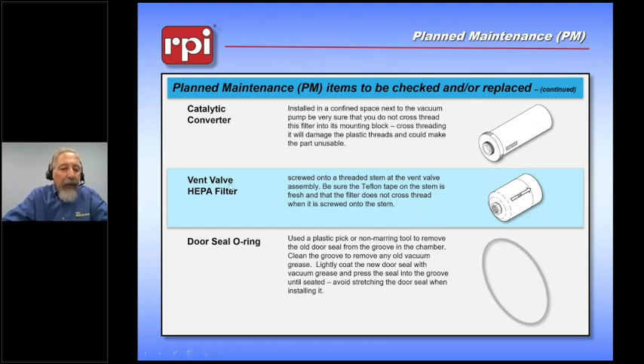Also included in the PM kit is a HEPA filter. This HEPA filter is what filters the main body of air that's allowed into the chamber when we vent the actual chamber. It does not take the air through that little disc filter I showed you earlier. This filter is located on the top of the machine as part of the venting and the pressure measurement system.